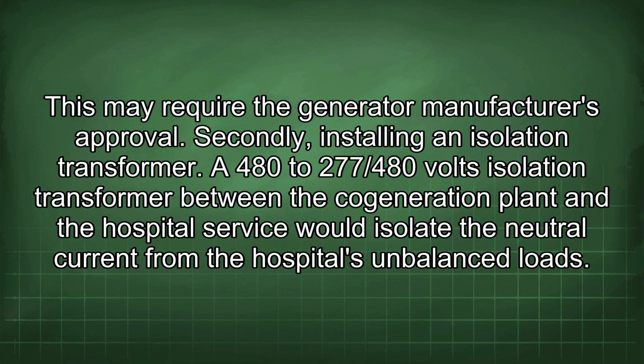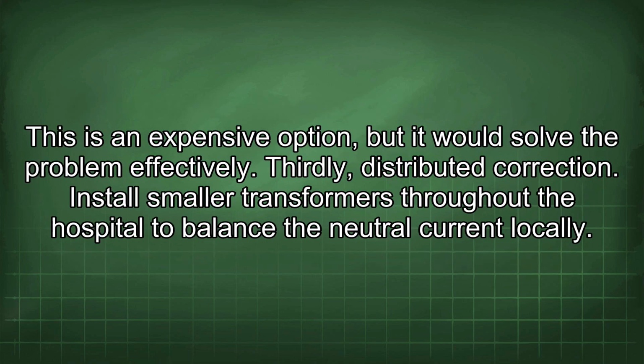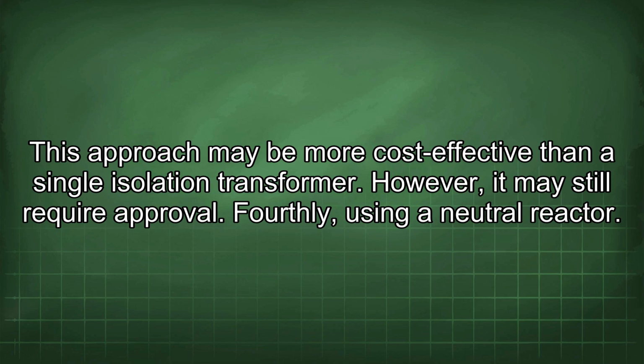Secondly, installing an isolation transformer. A 480 to 277/480 volt isolation transformer between the cogeneration plant and the hospital service would isolate the neutral current from the hospital's unbalanced loads. This is an expensive option, but it would solve the problem effectively. Thirdly, distributed correction. Install smaller transformers throughout the hospital to balance the neutral current locally. This approach may be more cost-effective than a single isolation transformer. However, it may still require approval.